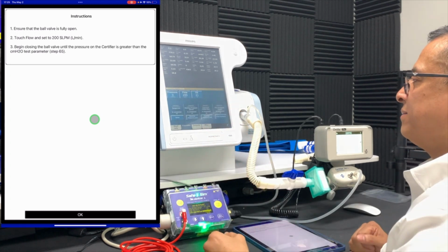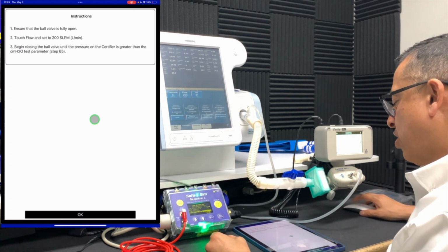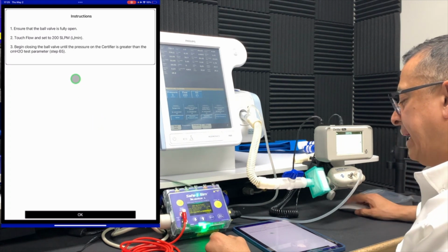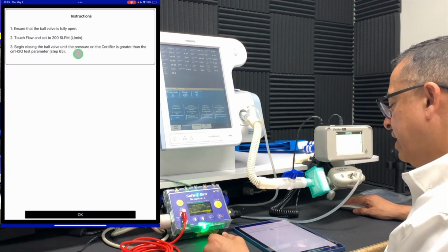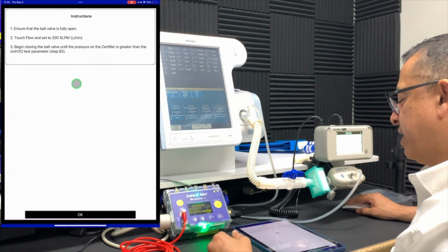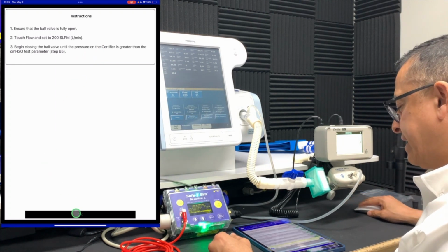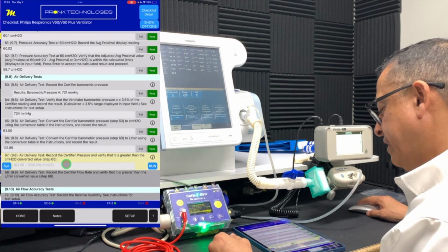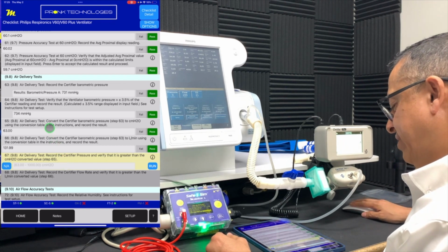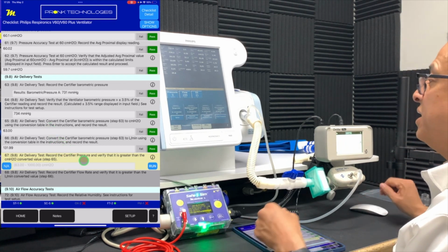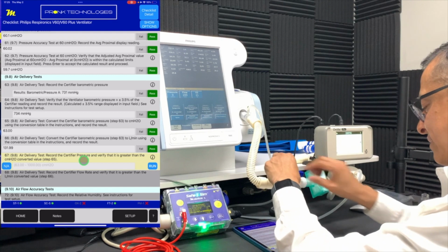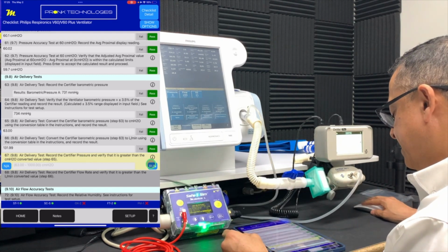And we've done that. Flow has started a curve. And now we're going to begin to close that ball valve until the pressure in the certifier is greater than the value on step 65. So we need to exceed 63. So I'm going to go ahead and do that. And I'm going to run this test.